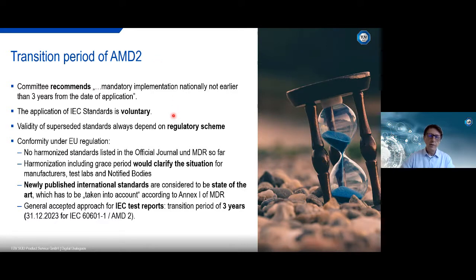However, the application of standards is voluntary, as you all know—it's not required by regulations—so it depends on the regulatory scheme of the market where you want to place your product, and how the transfer to new standards is handled there. In Europe, at the moment, we still do not have harmonized standards listed in an official journal under the MDR, as we had in the past under the MDD. This would have helped a lot, since it clarified until when an old standard revision could still be used and since when a new one needed to be implemented. However, as already mentioned, newly published standards have to be taken into account since they became state of the art.